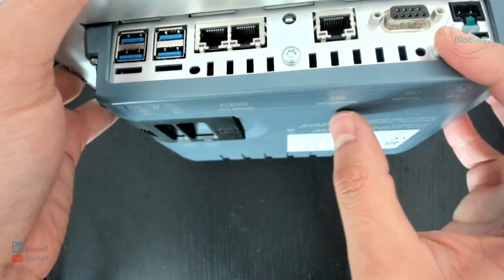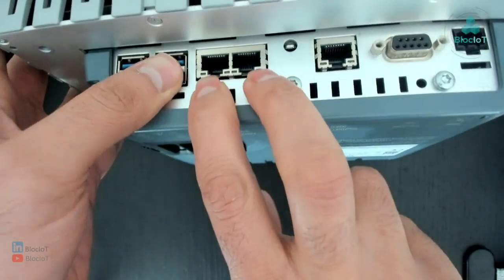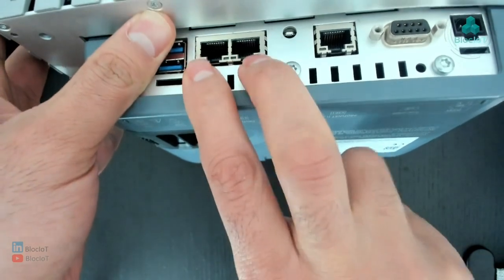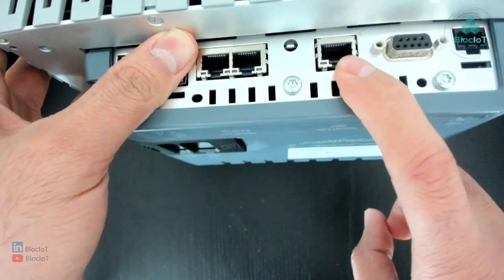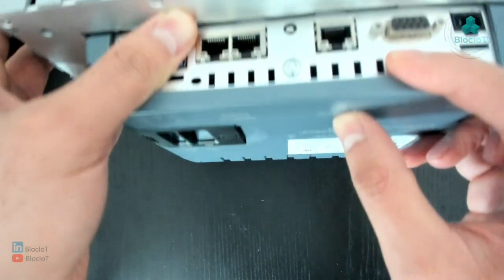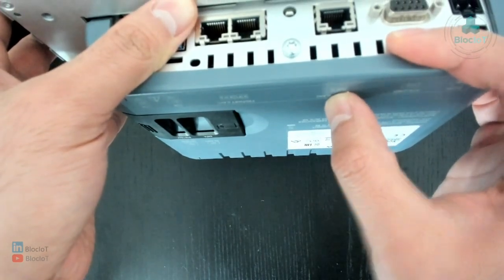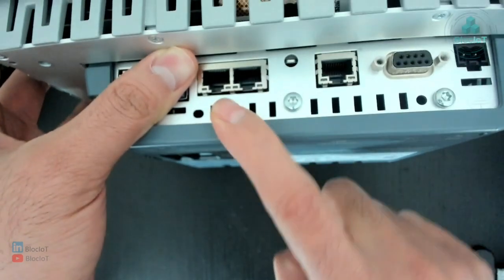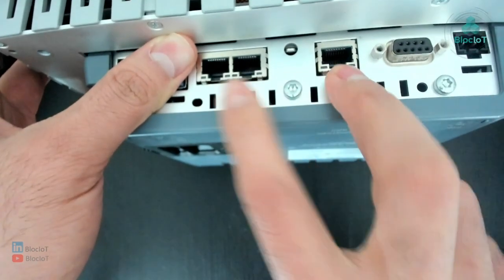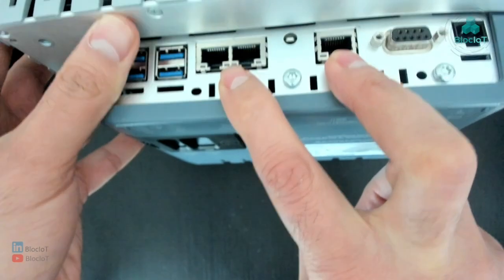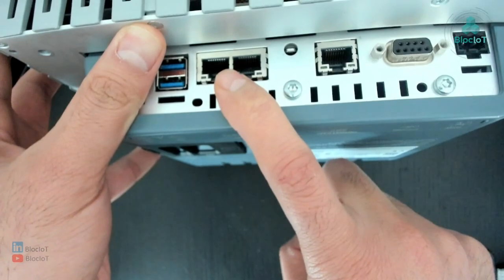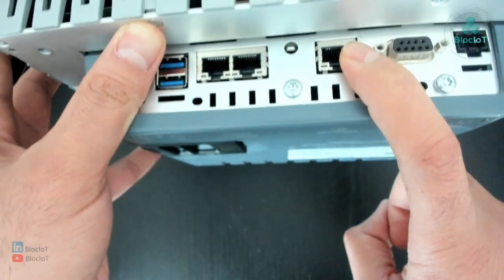And you have two sets of Ethernet ports. The X1, which is this one on the left side, is a two port switch, basically. So these two are the same. They have the same type of IP address. And the right one, the single one, which is called X2, if I'm not mistaken. Yes, let me read. Yeah, this one is X2P1, this one is X1P1, and X1P2. So these two ports are, or these two groups are totally separate. They get different IP addresses in separate subnets, which is very great. So let's say you can use this one on the left one for your PLC or OT network, and the right one for connecting to the internet, which improves the security significantly.